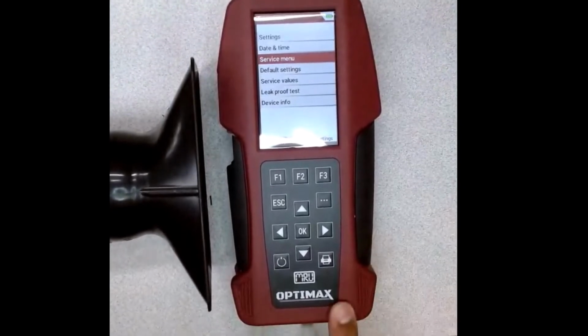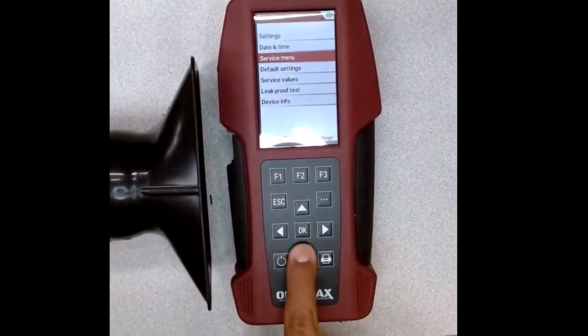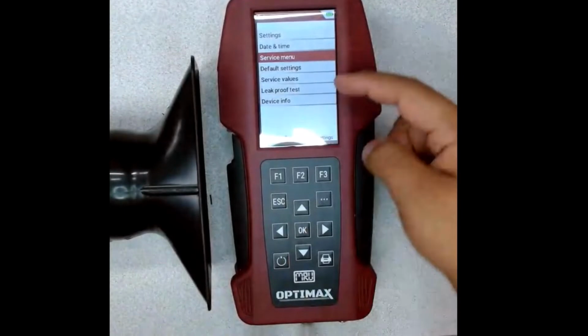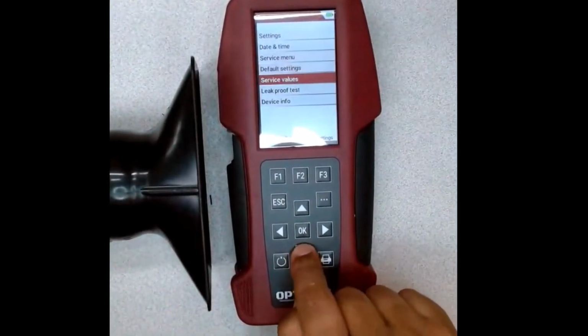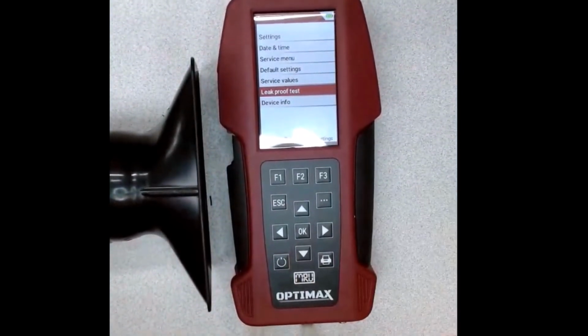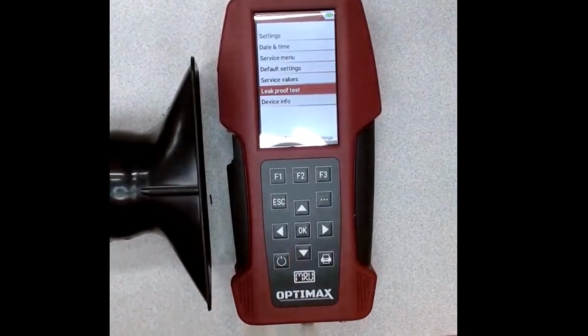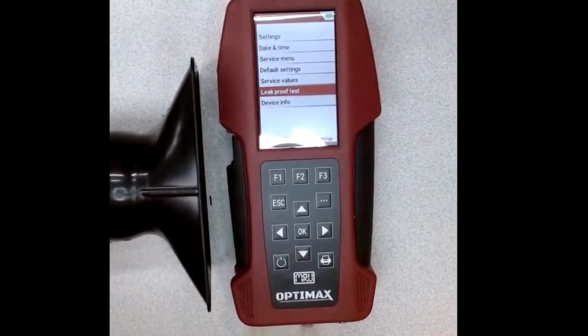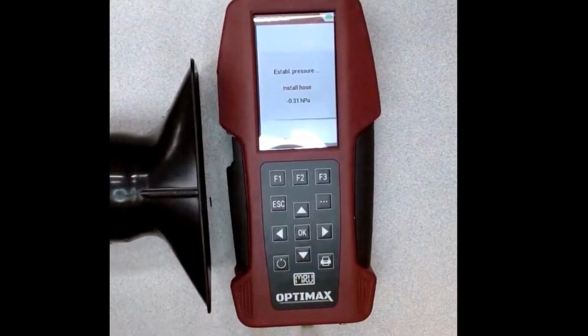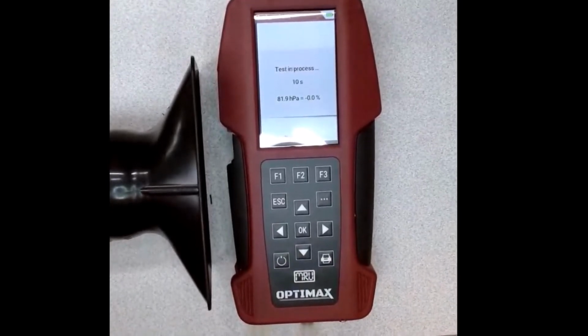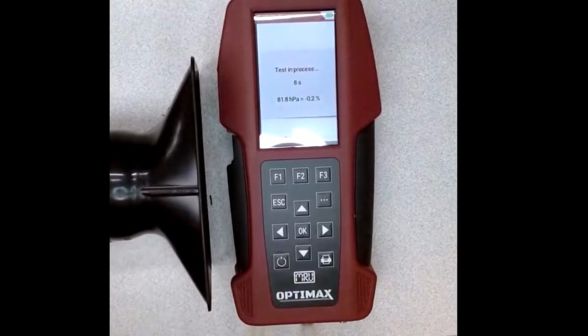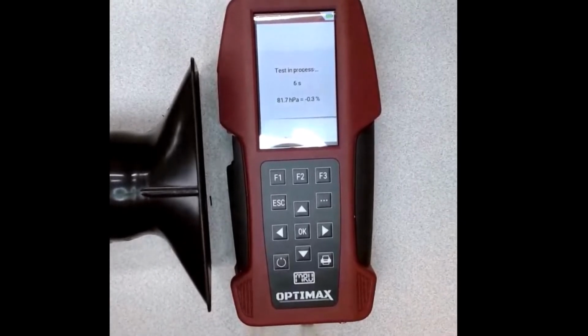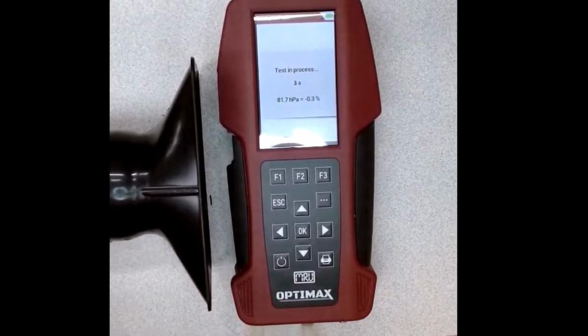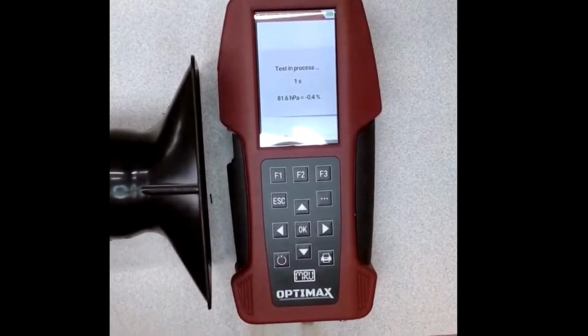So once the jumper is put in, we'll be in the extras menu, and we'll navigate down to leak proof test. It'll be the second to last menu option in the extras menu. Okay, and then we'll click on that. We'll press enter. So what it'll do is it builds a vacuum and then does a 10-second test and measures how much of the vacuum is lost.